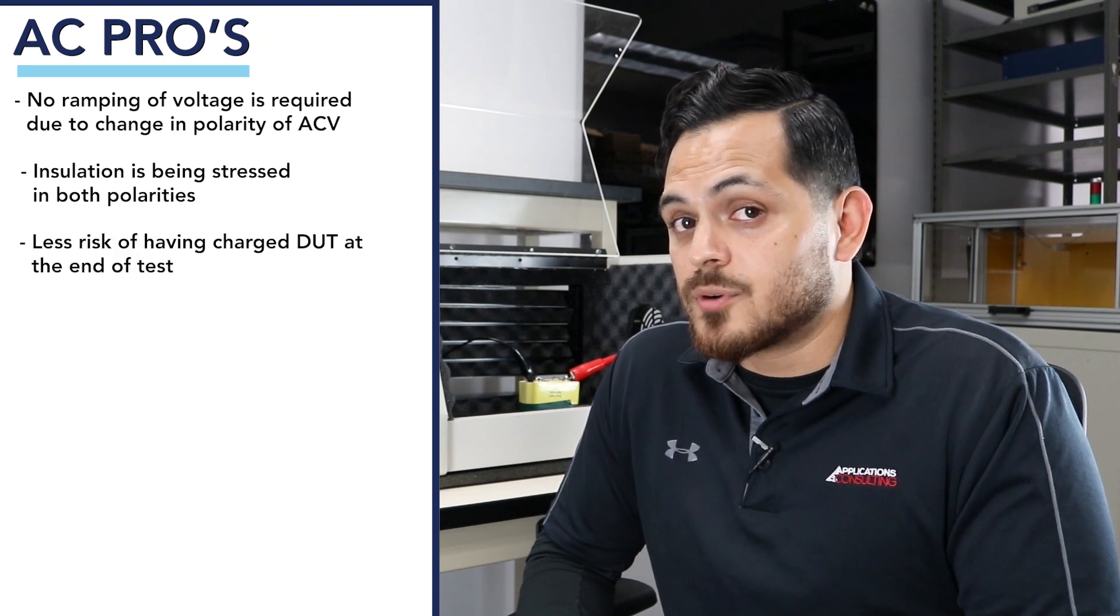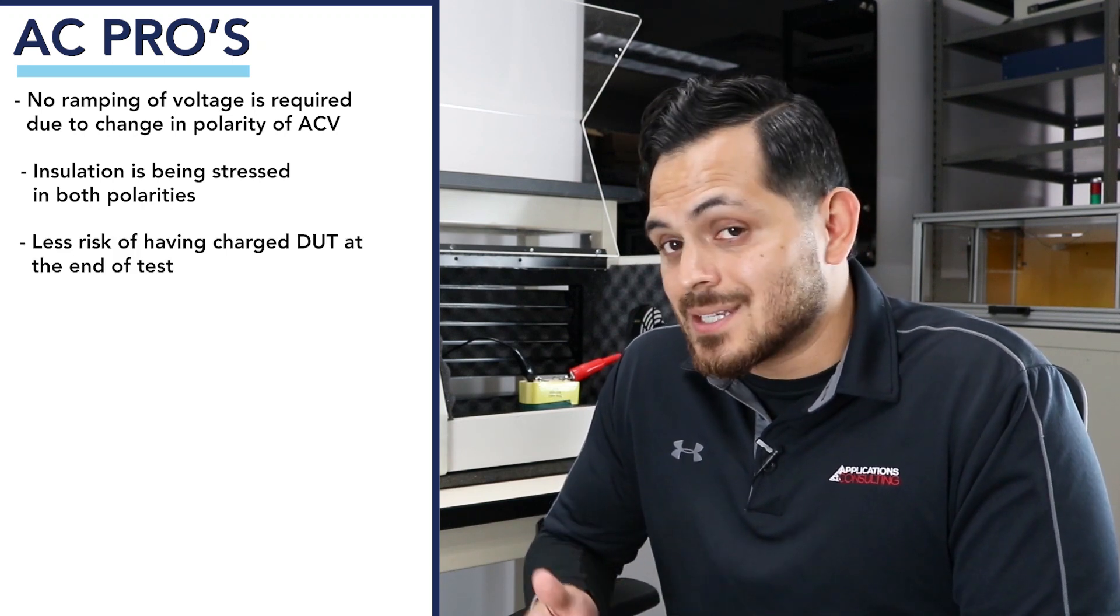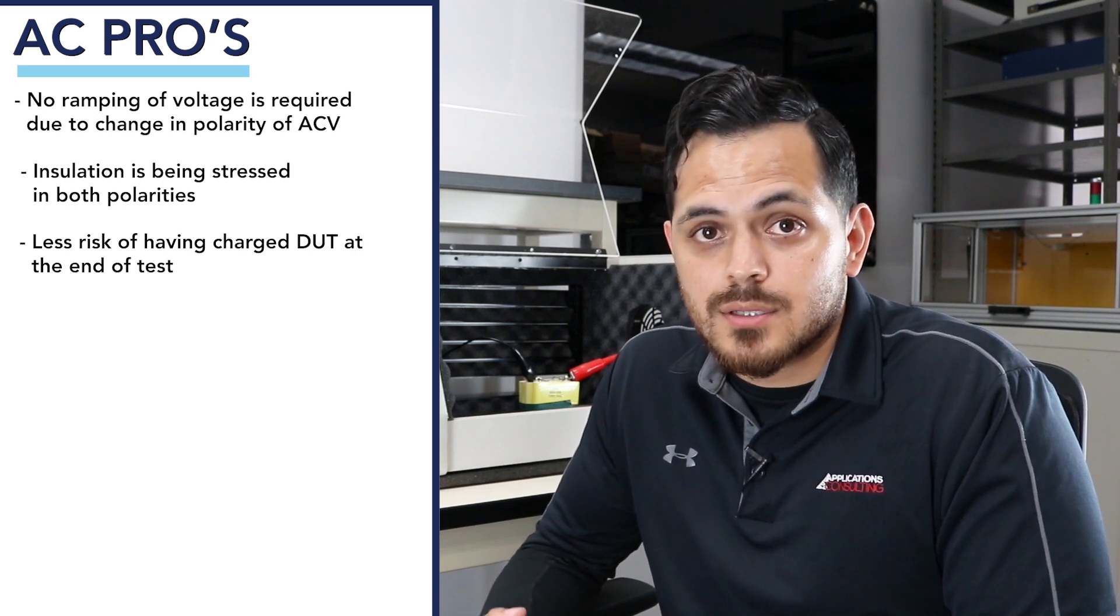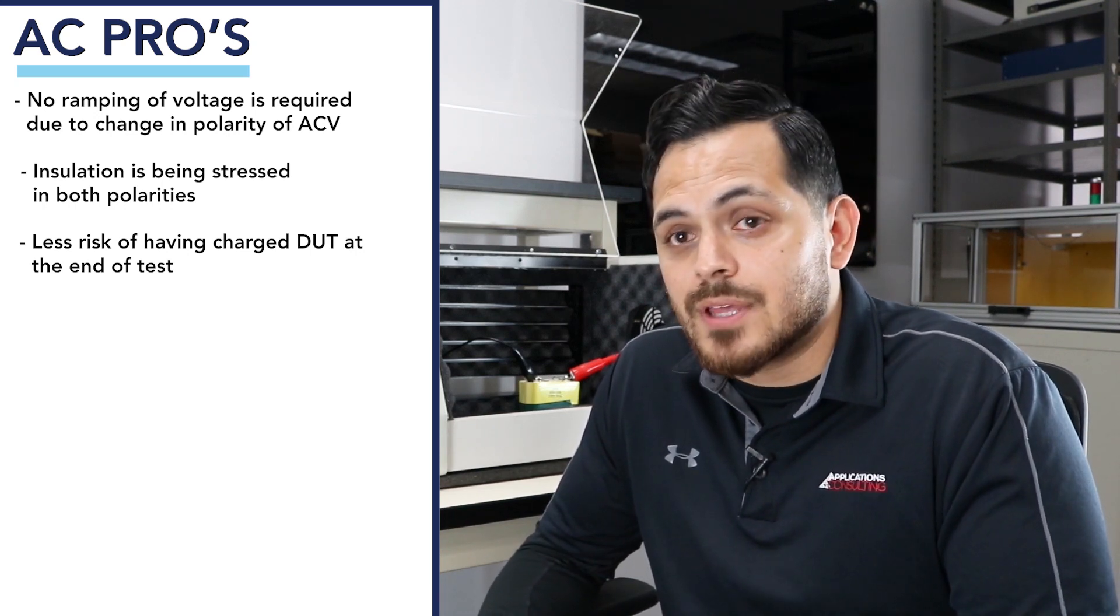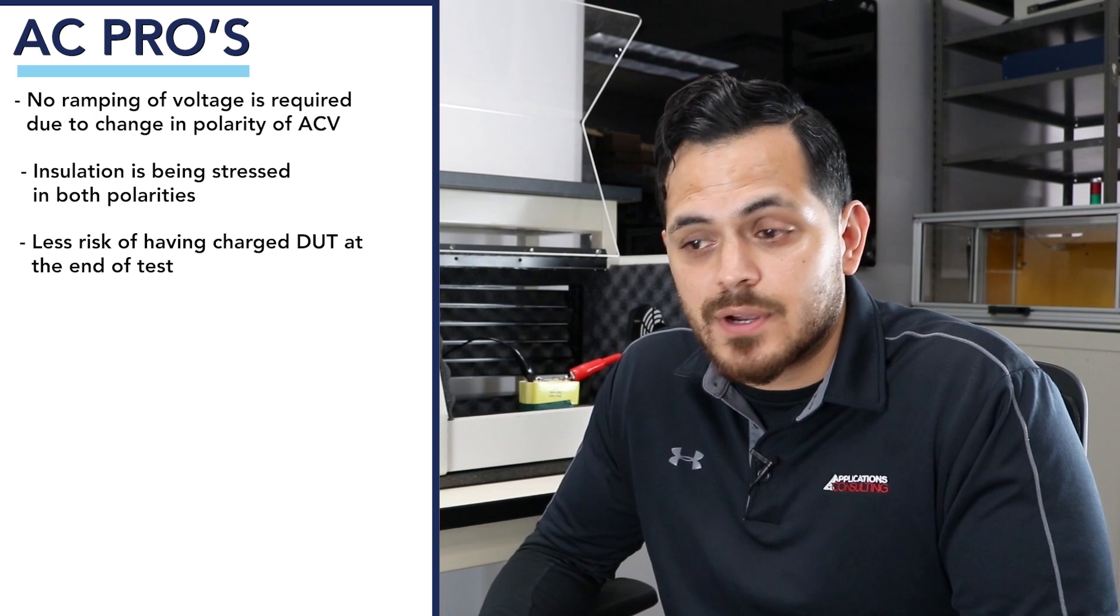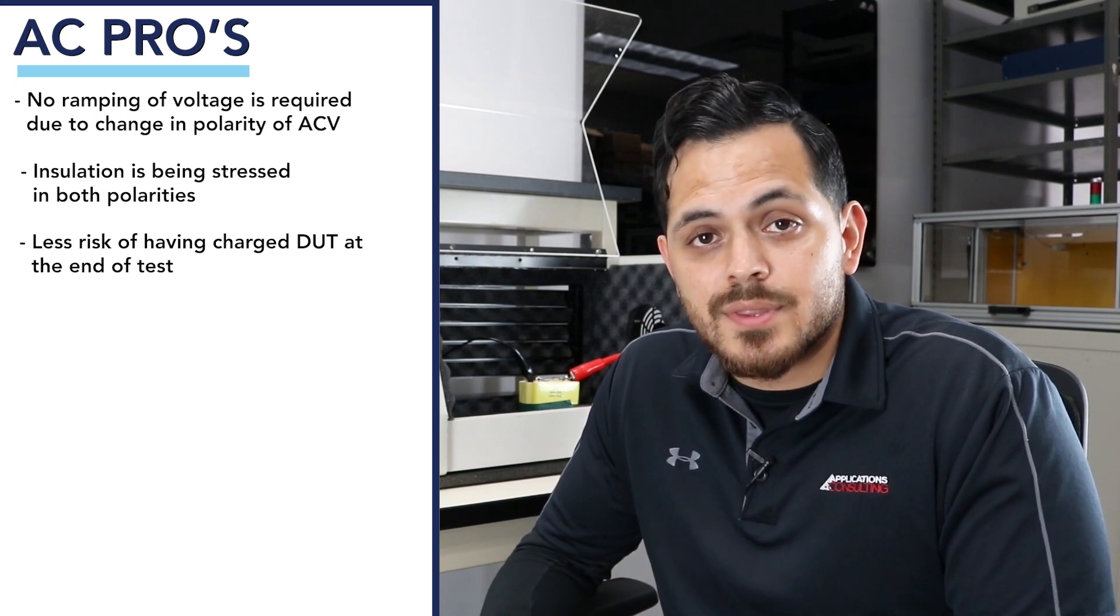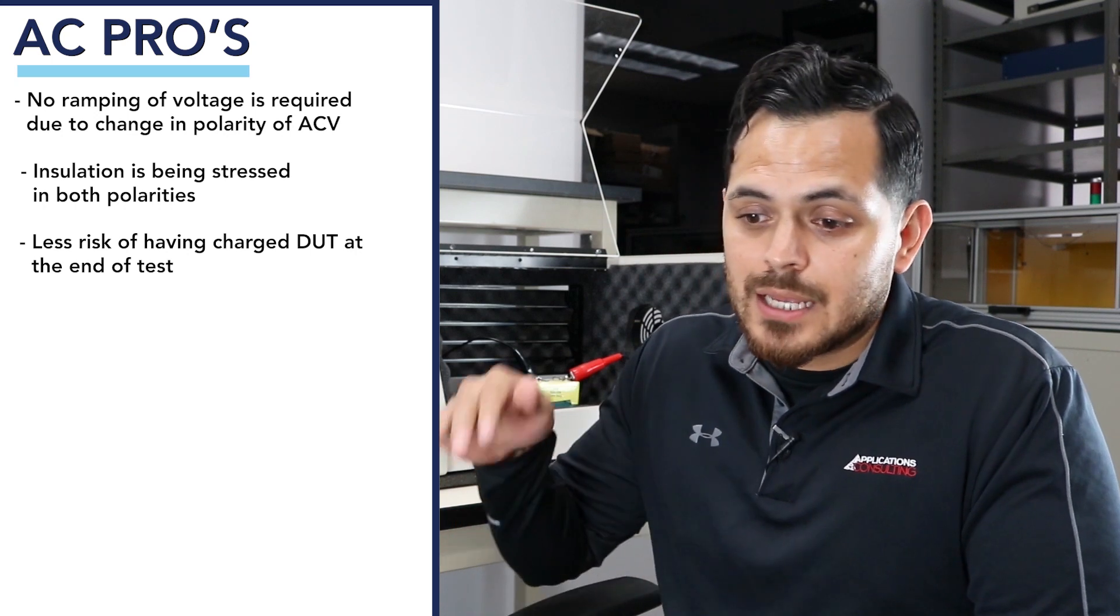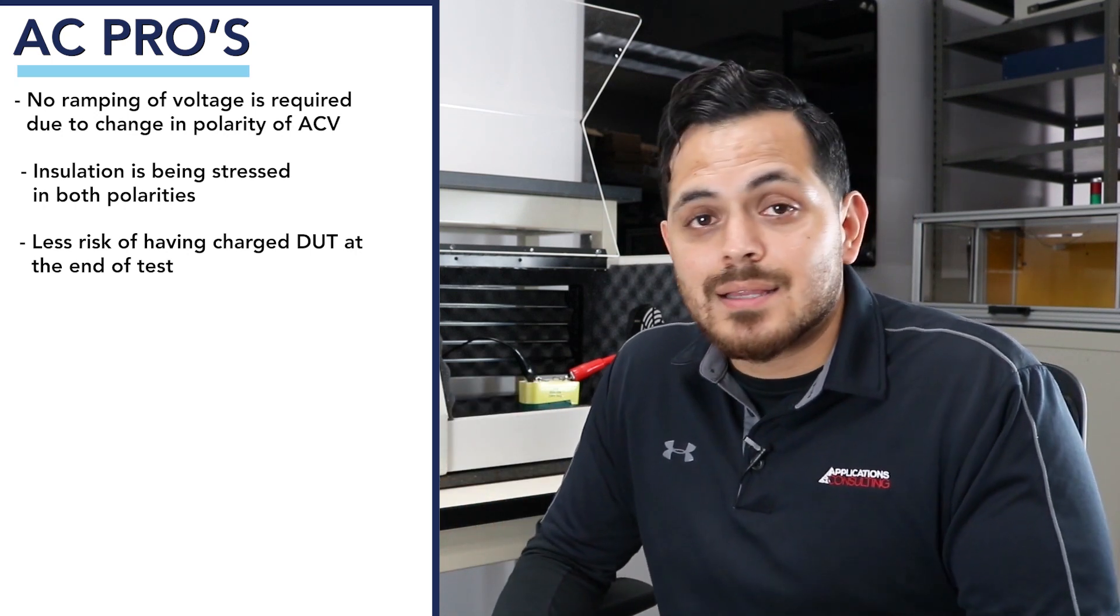Another great thing about AC contrasting with DC is when you're performing a DC test at the end of that test you're probably left with a charged product, and so it's imperative that you have some sort of procedure to verify that you're discharging everything that just got hypotested.